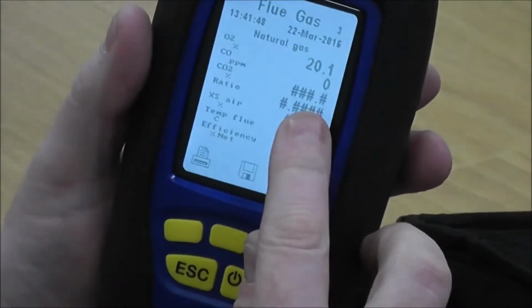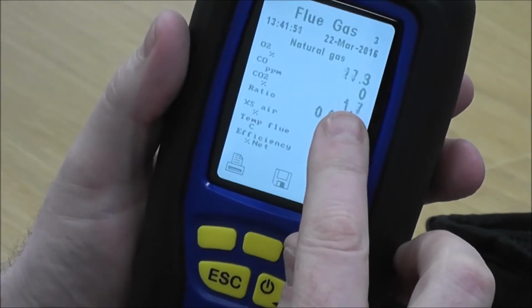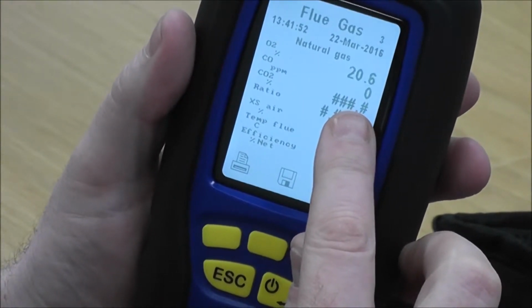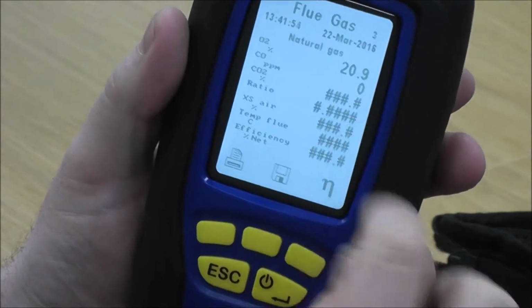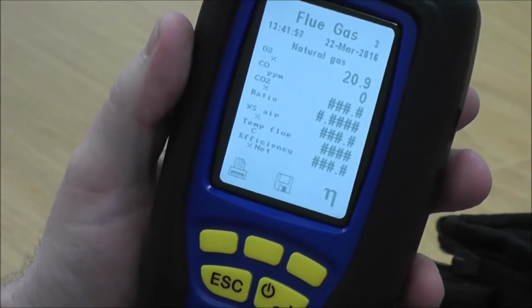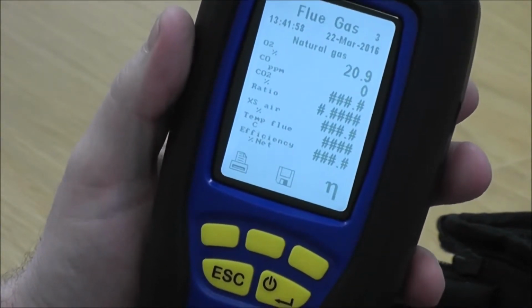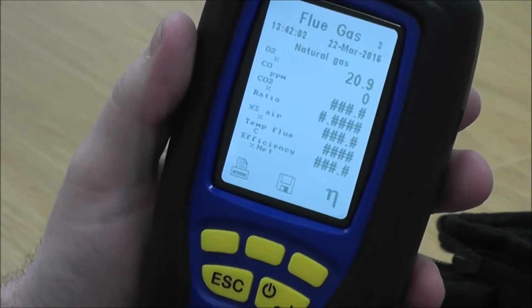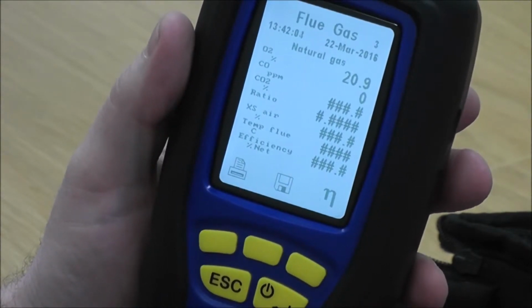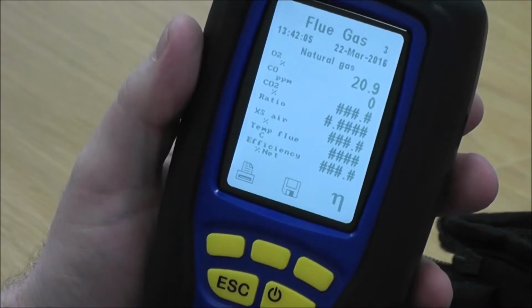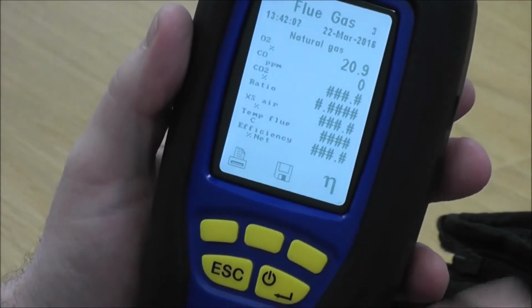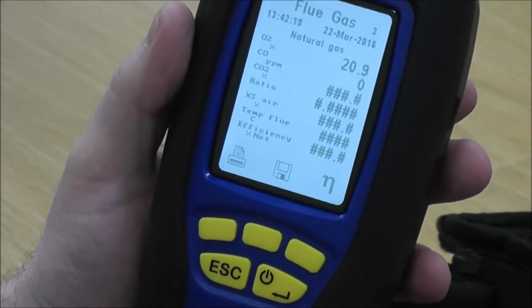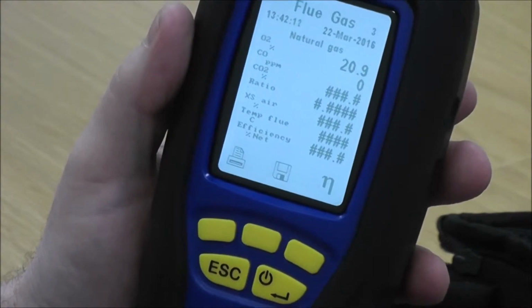And you'll see your O2 reading drops that time to about 18%, but you'll see that it recovers quite quickly. Now that tells me that the sample's been taken from the pump through over the manifold to the sensors, and they're reacting in a timely fashion, and they're recovering as well, which tells you there's no blockages, the pump's strong, and you've got no moisture on the internal tubes.